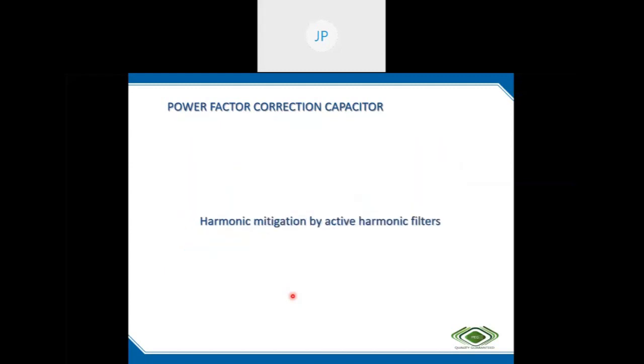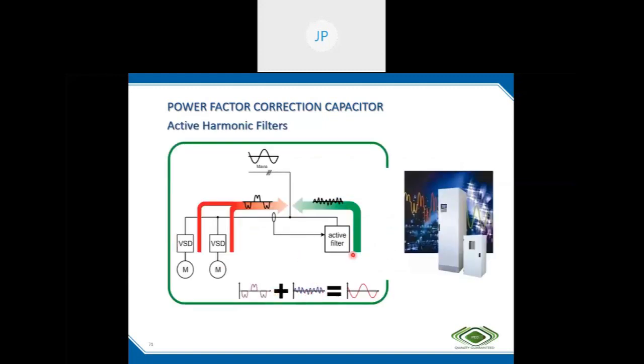Now, the next solution is the active harmonic filter. An active harmonic filter is nothing but an electronic device generating a signal equal and opposite to the harmonic content. So this is the nonlinear load in the system. Our supply source is sinusoidal, but its load current is distorted. That means it is injecting harmonics.